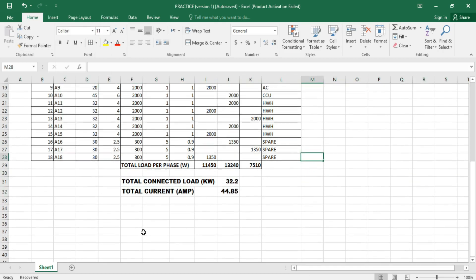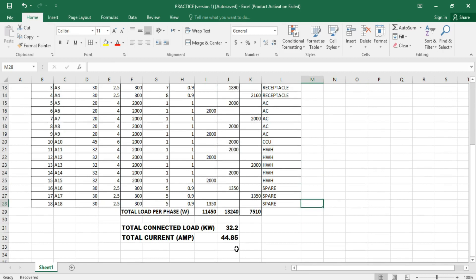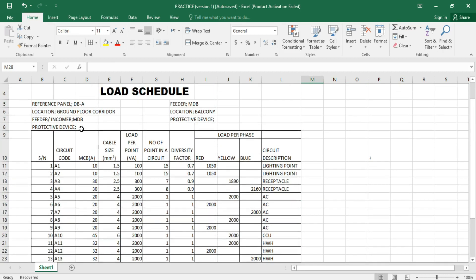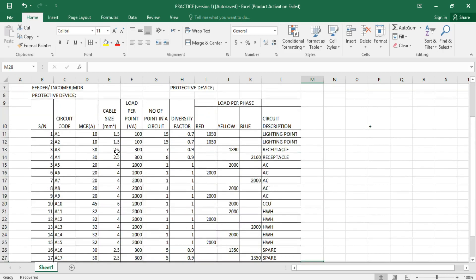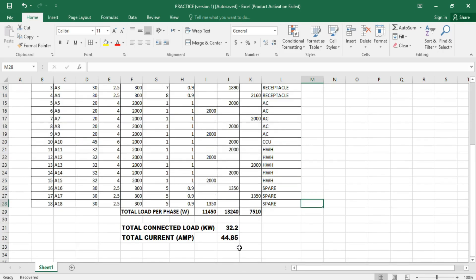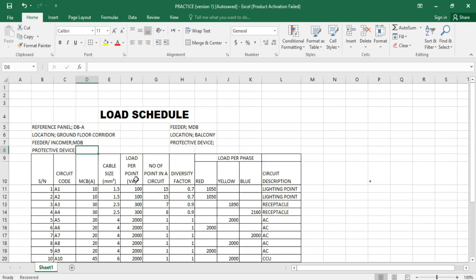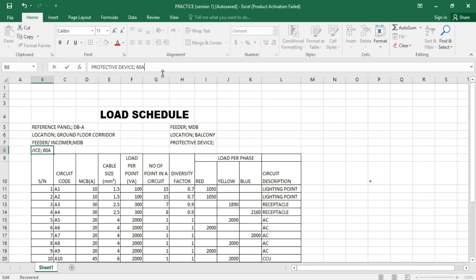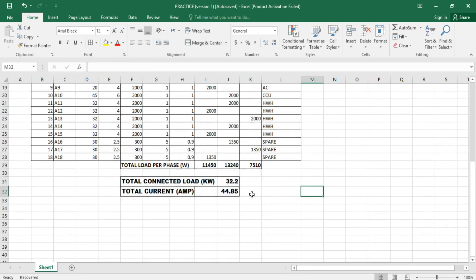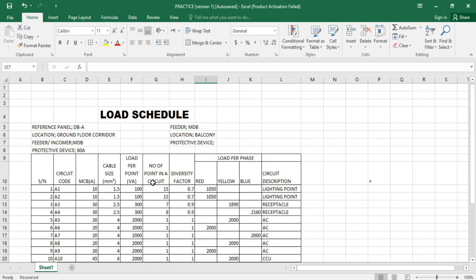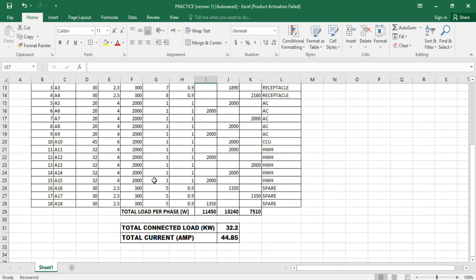So we're having 44.85 ampere total current. Our total connected load is 32.2 kilowatts and the total current for the building is 44.85 ampere. Based on this, we can be able to specify our protective device. The next standard protective device greater than 44.85 is either 50 or 60 ampere, so let's specify our protective device to be 60 ampere. This is the process of creating a load schedule.